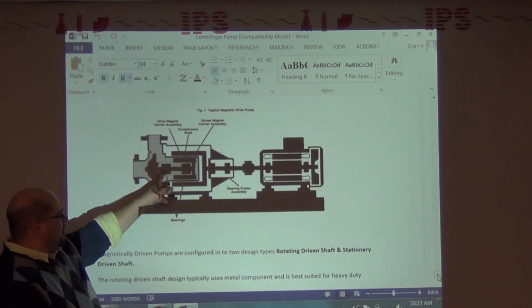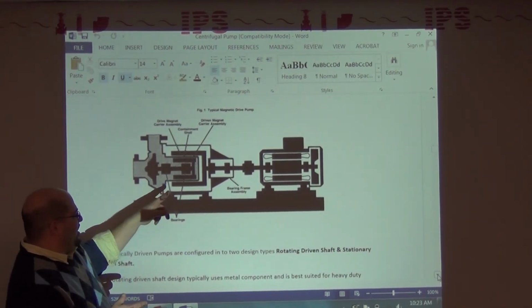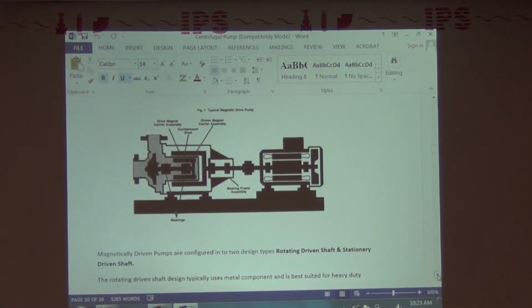Well, that's your hiccup, is you are now putting your main bushings into that process fluid, so you have to be particular. Now, pumps can pump solids, but solid is a very wide term. What's the type of solid, if we're going to do that? Theoretically, we're using that fluid, sending it down through the pump to lubricate everything, so we try to stay away from solid applications. Sometimes you run into it. We have lime or brine solutions that crystallize. Some of those we'll do with this pump, but we don't want anything that's overbearing.